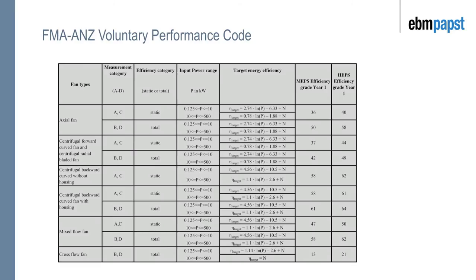Centrifugal fans are not only defined by their blade type but also by their efficiency. Here in Australia you can go to the fan manufacturer's website www.fmaanz.com.au, where you'll find a code of practice for minimum efficiency standards and high efficiency standards for a range of different fan types. For example, the defined minimum efficiency grade for a mixed flow fan is 47, a forward curved fan has a grade of 37, whereas a backward curve fan is much more efficient with a minimum efficiency grade of 58.